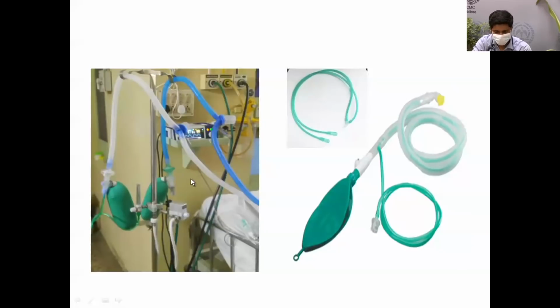The advantage of this machine is you can give a higher FiO2, but the disadvantage is it consumes a lot of oxygen, where your flow can vary from 40 to 70 liters. So it's better to use this machine early, and then if the oxygen requirement is going up, to change over to a ventilator mode of NIV in a ventilator.